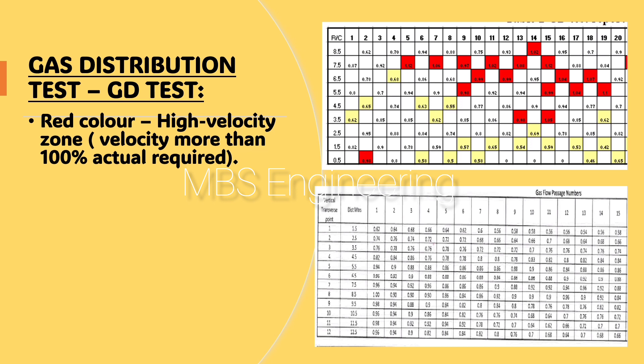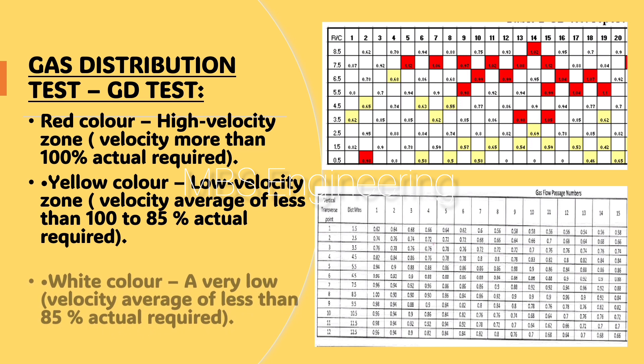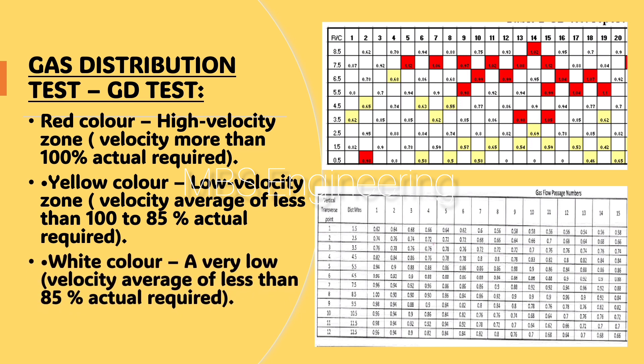The readings are tabulated with all details like average velocities and deviations, and graphs are plotted and analyzed. Please refer to the GD screen sample readings for better understanding. Red color indicates a high velocity zone — velocity more than 100% of actual required. Yellow color indicates a low velocity zone — velocity average between 85% and 100% of actual required. White color indicates a very low velocity zone — average less than 85% of actual required.